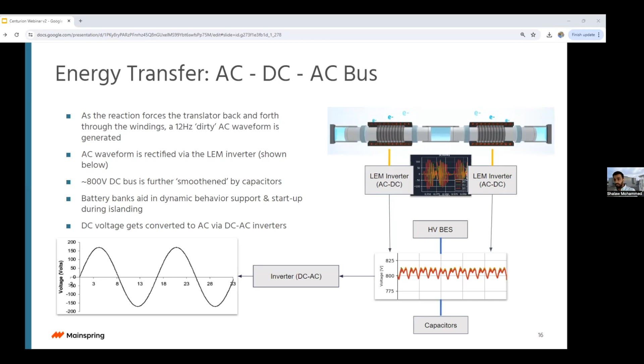In our case, it's Dyna Power inverters, 125 kW per each core, so 250 for the entire package. So what the end result is, we get 480 volt, 60 hertz electricity. This slide just summarizes what I just talked about. So you take this waveform that's not necessarily usable, you convert that to DC, DC back to AC, and you're getting your required waveform.